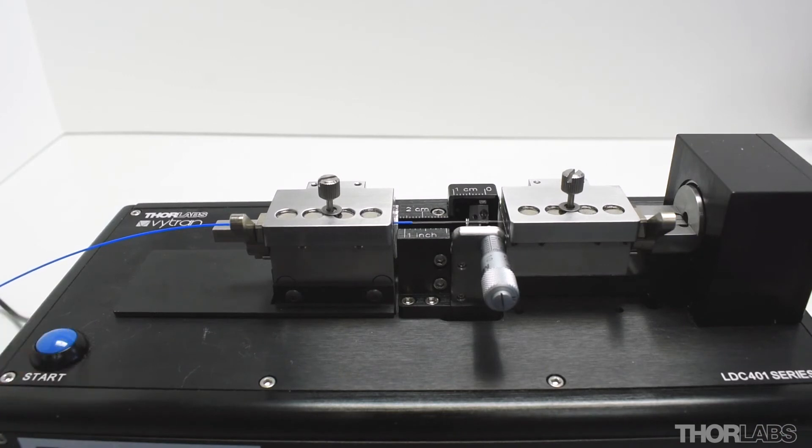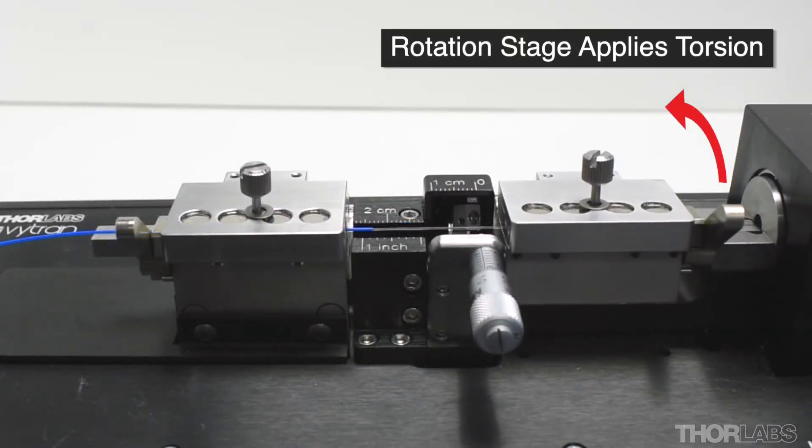Press the start button again to activate the cleave. First, the rotation stage will rotate the right-hand side fiber holding block by the angle set in the cleave file. This will apply torsional stress to the fiber.